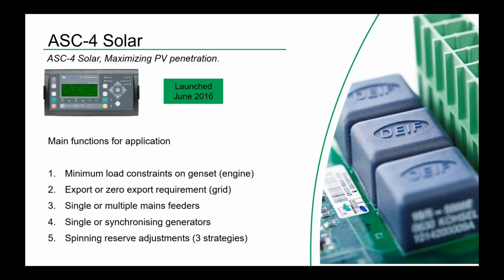If we should point at some main functions, then I have listed a couple of main functions here. Number one main function is, of course, the minimum load on the generator or engine. We need to be able to maintain the minimum load, as Christoph also mentioned. This is key for the health of the engine, to avoid problems with glazing of cylinder liners, for instance. We have export requirements, zero export requirements also when you are grid parallel. Typically, zero export is a must. That is seen in the majority of the grid-tied applications, but we can also set an export set point depending on your agreement with the utility company.